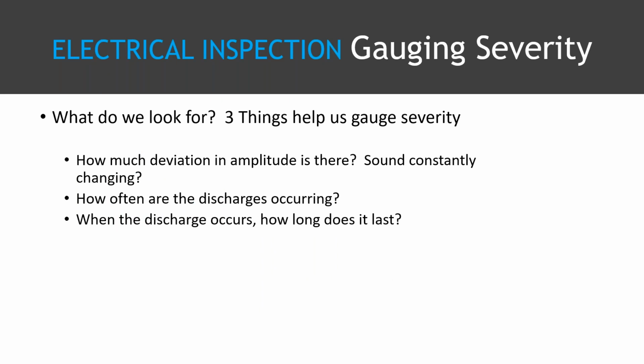So the three things everybody wants to know: how bad is bad? How do we gauge severity when we hear something? There are really three things that help us gauge severity. One is how much deviation there is in the amplitude—is the sound constantly getting louder and softer? That tells us it's getting worse. How often do we hear those pops or cracks? The more often we hear them, the more severe that failure mode is. And when we hear those pops or cracks, how long does the discharge last? The longer it lasts, the more likely you're in severe tracking, or already in an arcing situation. So look at those three things: amplitude deviation, how often the discharges occur, and how long they last when they occur.